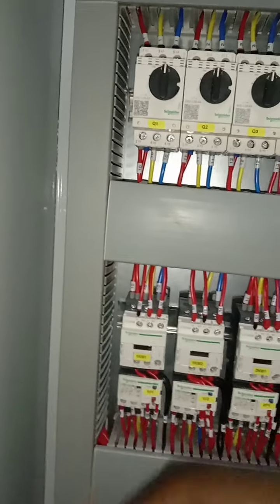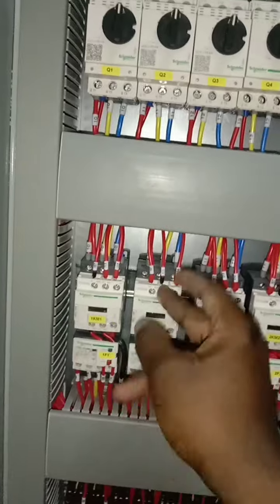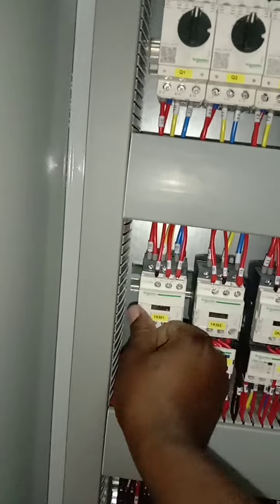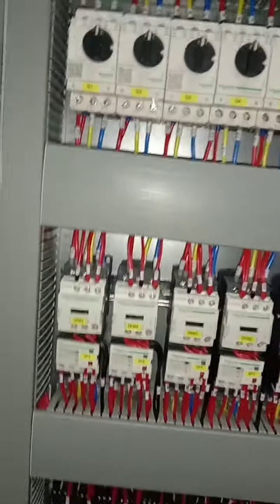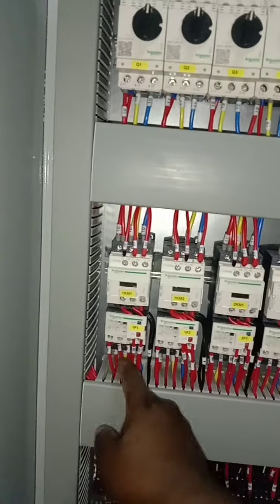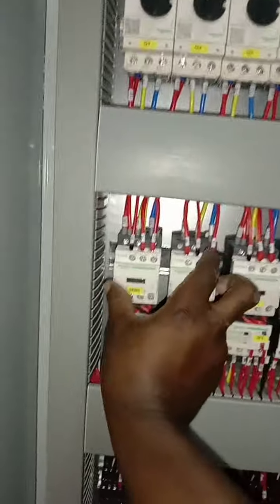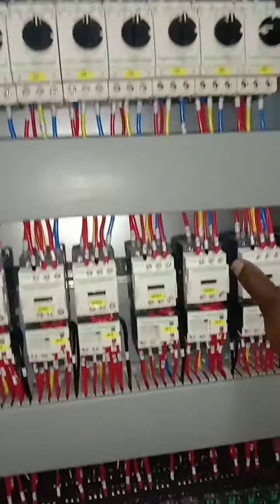Once it's powered, we know how contactors function, because these are two-speed motors. So this KM1, KM2 represents one motor. This is a two-speed starter, as I mentioned previously. From here it goes and feeds the motor from the output. So the two contactors will have the two different runs going to the motor. So we have motor 1, motor 2, motor 3, motor 4.